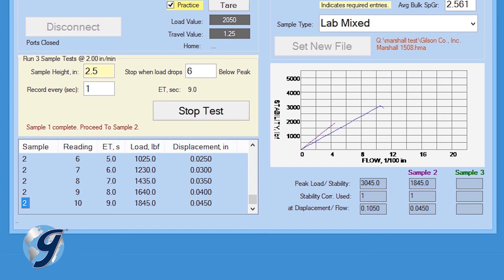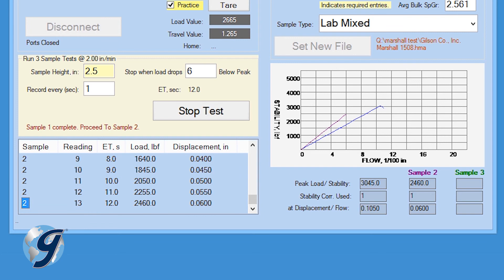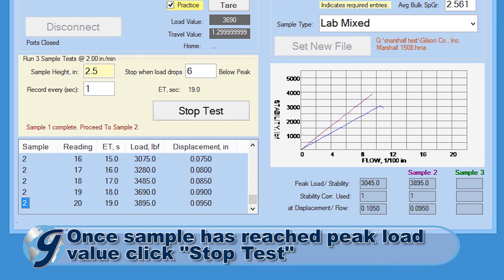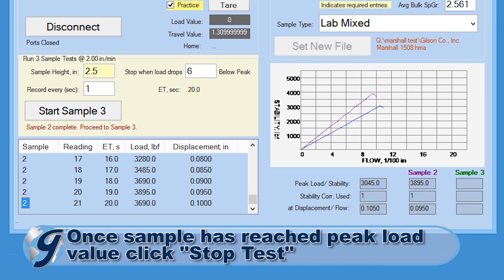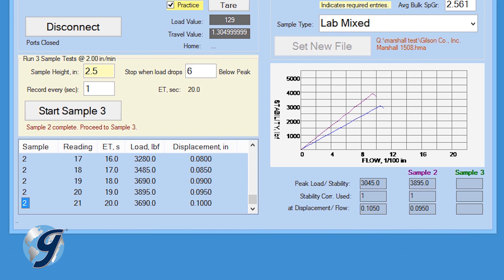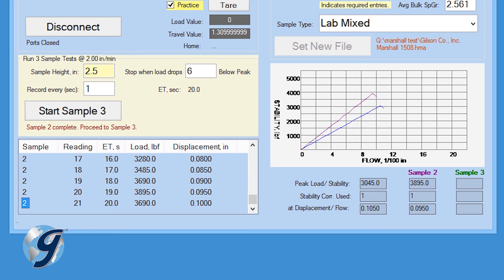Test data for each sample are displayed in the bottom right of the software program. Once the second sample has reached its peak load value, click stop test and the data will stop being recorded. If a load drop value was entered in the stop when load drops below peak field during the test setup, the load will automatically stop and the data will stop being recorded. Next, lower the platen by clicking on the down button on the load frame. Now remove the second sample.